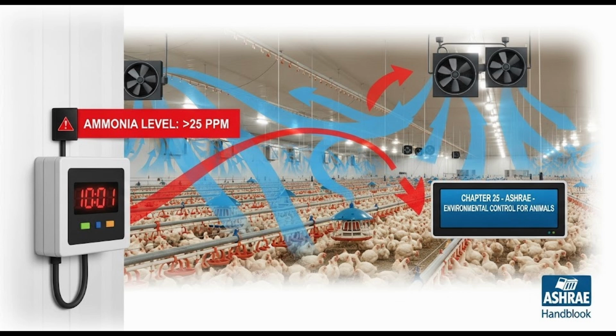That's exactly right. It's a logic curve. So in cold weather, you might think ventilation is mostly about temperature, but it's primarily driven by moisture control. Moisture, really? Yeah, keeping humidity below a certain point, usually 70 or 80% RH, to stop condensation forming on surfaces. And also keeping contaminants low for air quality. This nearly always means you need supplemental heating to maintain the target temperature while you're bringing in that cold, drier air. Okay, so cold weather, moisture and air quality first, heat second.